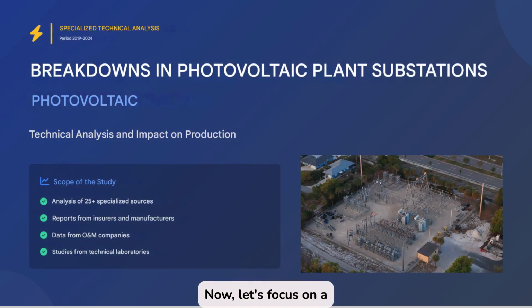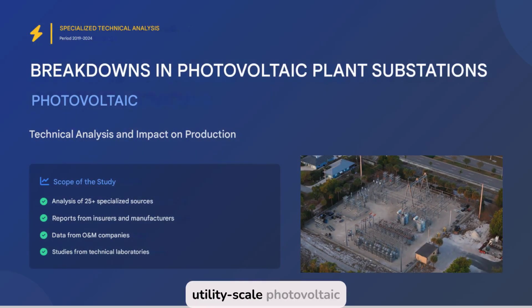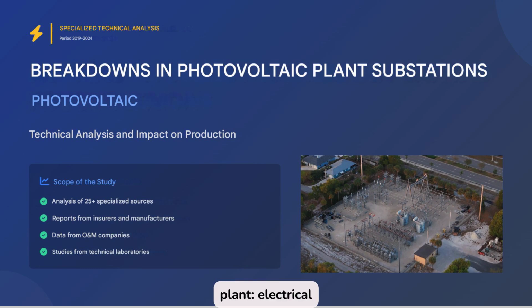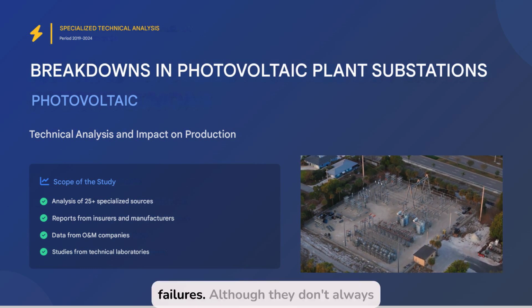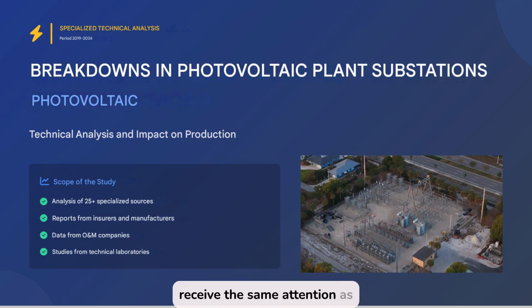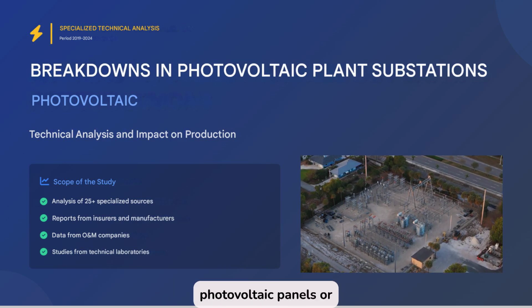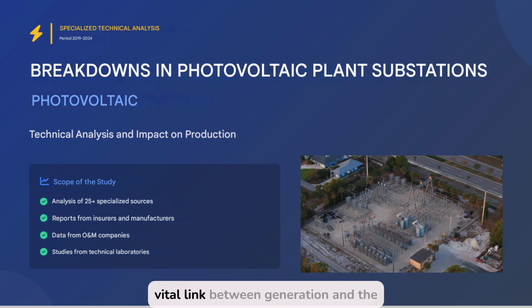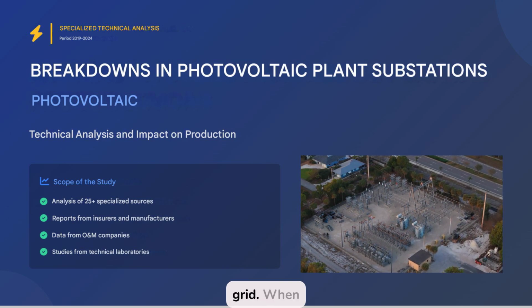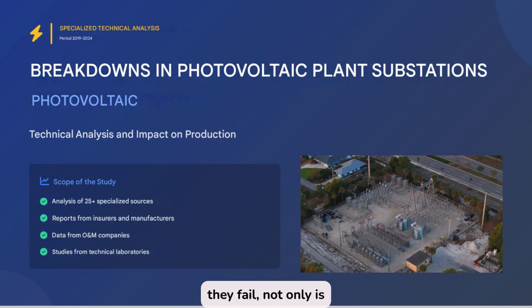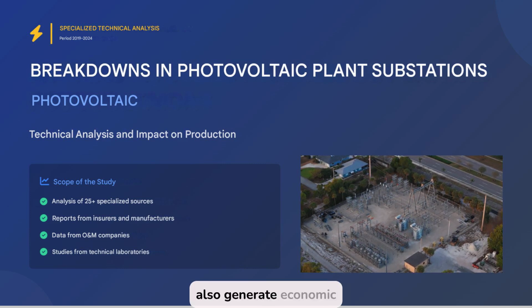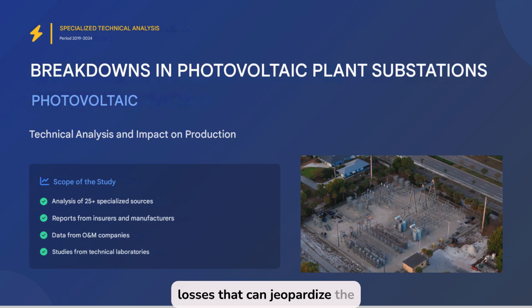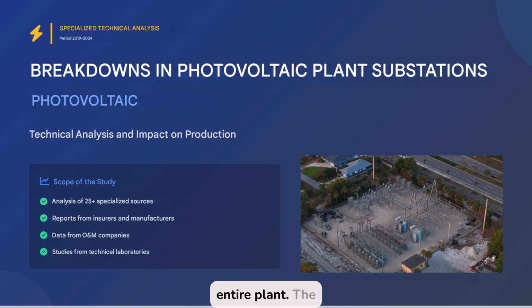Now, let's focus on a key issue for any utility-scale photovoltaic plant: electrical substation failures. Although they don't always receive the same attention as photovoltaic panels or inverters, substations are the vital link between generation and the grid. When they fail, not only is production interrupted, but they also generate economic losses that can jeopardize the financial viability of the entire plant.